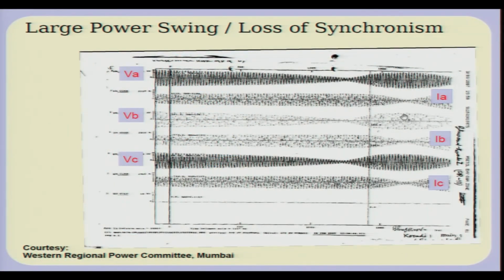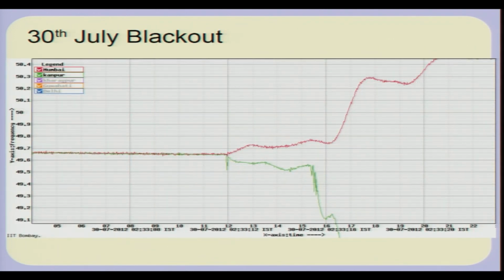You see similar signatures for voltages. These are the voltages for a disturbance which occurred more than a decade back in western India. You also have in 2012 there was a blackout, and there too the system lost synchronism. So, in two parts of the system the frequencies, the system split apart, that is, it could not pull back into synchronism. So, this is something which occurs in a synchronous grid.